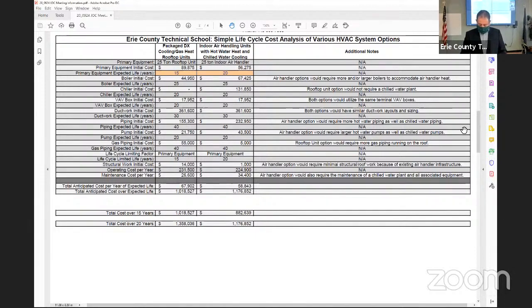And if you look down at the bottom, total cost over 15 years, looking at both systems, you're looking at significantly less with the air handling units. And again, one of the main reasons for this is the initial installation cost. With the rooftop units, you have to include the structure, other things that you have to modify, where with the interior air handling units, you don't, because that structure is already in place.